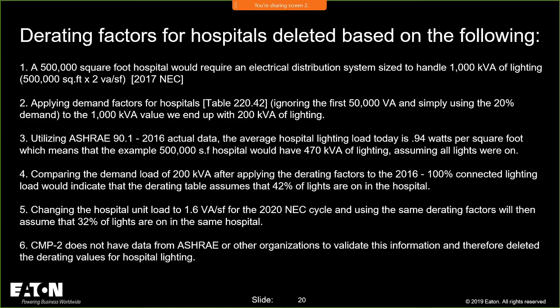For example, this was in the substantiation for deleting those factors. This was what the submitter supplied as an example. They took a 500,000 square foot hospital requiring electrical distribution sized to handle 1,000 kVA of lighting, based upon 2 VA per square foot in the 2017 code. If you applied the demand factors, you'd end up with about 200 kVA of lighting in the 2017 version. Utilizing the 2016 version of ASHRAE, the average hospital lighting load is about 0.94 watts per square foot, which means the example of 500,000 would yield about 470 kVA of lighting, assuming all lights were on. Comparing the demand of 200 kVA after applying the derating factors in the 2016 with 100% connected lighting load, it assumes that 42% of lights are on in the hospital.